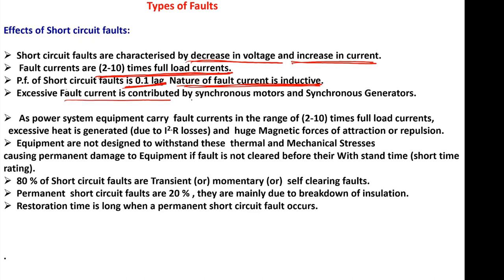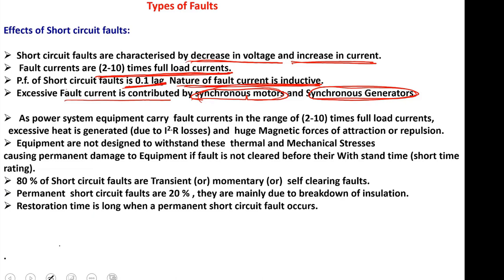The fault current is mainly contributed by synchronous motors and synchronous generators — both are sources for fault current. As power system equipment carries fault currents of 2 to 10 times full load currents, excessive heat is generated due to I²R losses, and huge magnetic forces of attraction or repulsion occur.